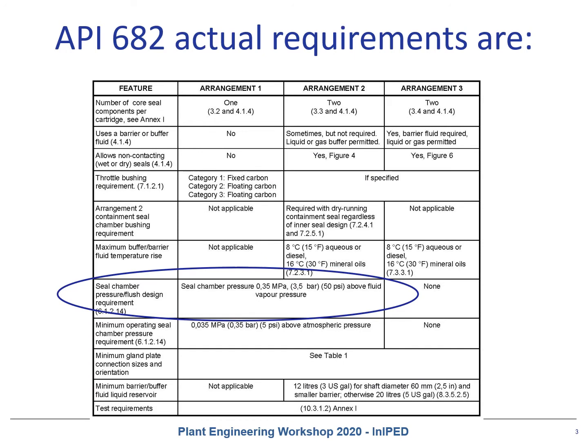The API 682, the global standard for mechanical seals, defines light hydrocarbons as a hydrocarbon liquid which will readily boil at ambient conditions. API 682 applies different rules, like the 30% vapor pressure margin, or the 20 Kelvin rule, or the actual requirement of 3.5 bar — which means 50 psi — seal chamber pressure above the fluid vapor pressure.